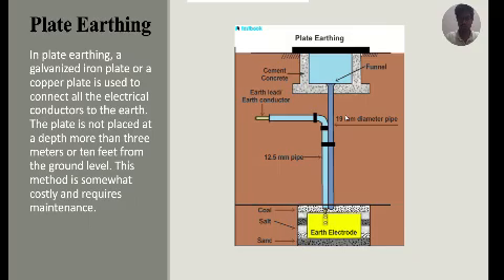The second type of earthing is plate earthing. In this type of earthing, a metal plate, either galvanized iron or a copper plate, is used to connect all the electrical conductors to the earth. The plate is placed at a depth of more than 3 meters or 10 feet from the ground, and it is connected to electrical conductors that transmit fault currents safely into the earth. The diameter may vary from 12.5 millimeters to 19 mm, and it should not be placed more than 3 meters or 10 feet from the ground.